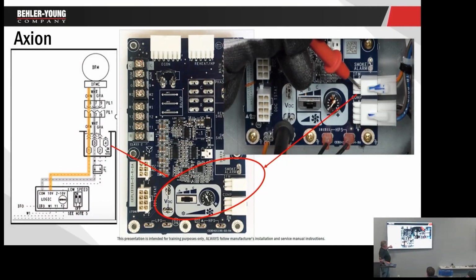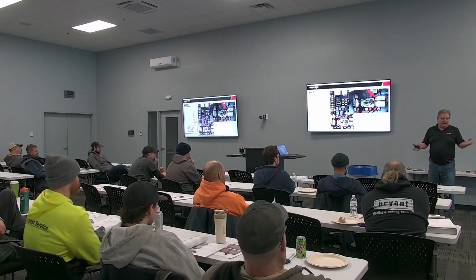So I can come back to the gas control board and check, do I have 20 volts on the IFO terminal, which is the indoor fan output? If I do, then this board is bad. If I don't, the gas control is bad. I don't know if you've seen it, but every so often I've had it happen, you get a crack in the solder, and you push on the board and all of a sudden the blower comes on. And you look on the back and there's a little brown spot where it's been overheating. Okay, any questions on this? Really pretty simple, again, kind of knowing how it works.